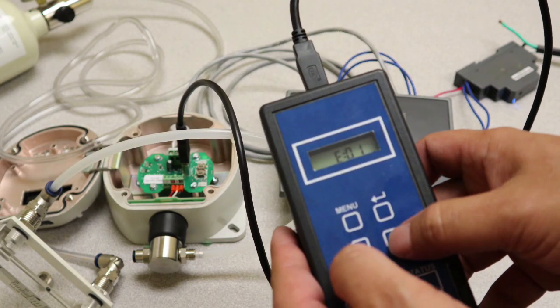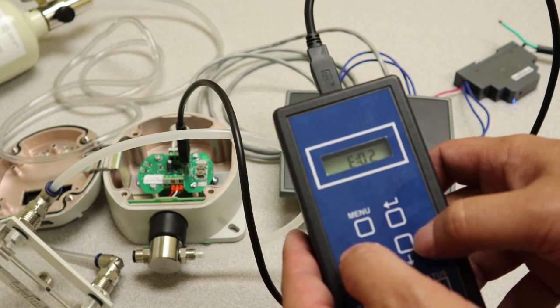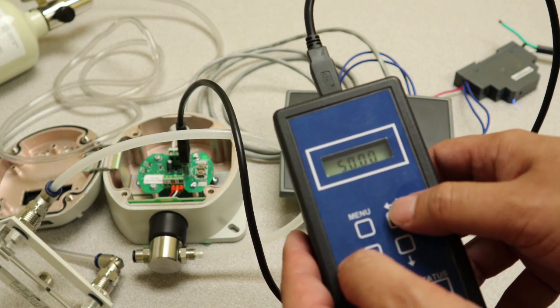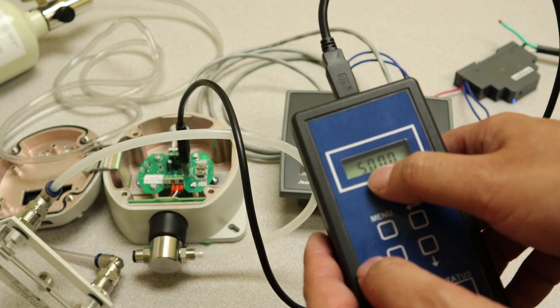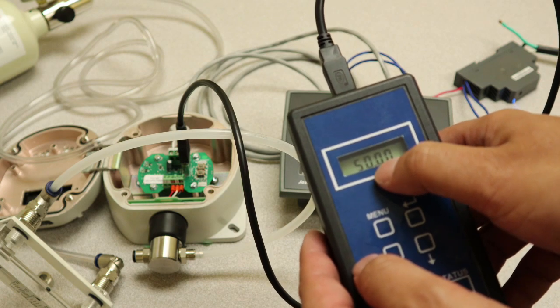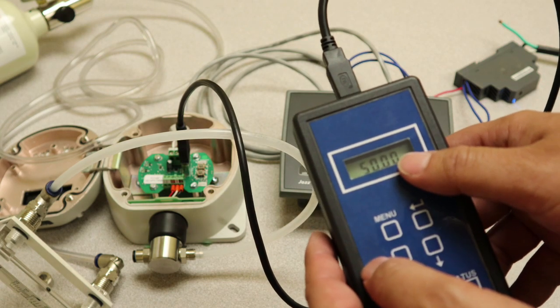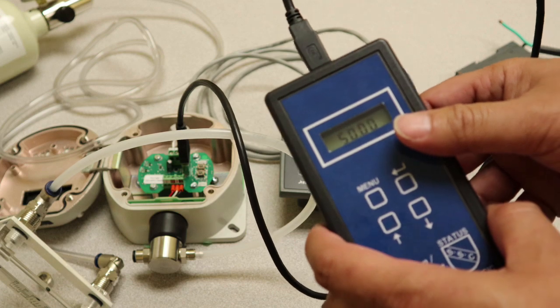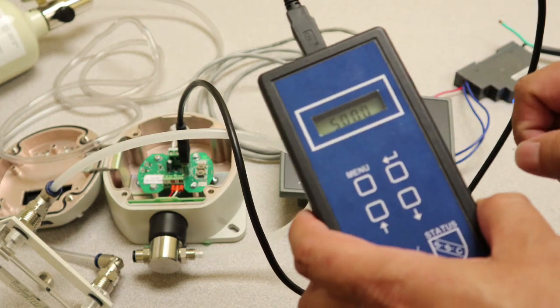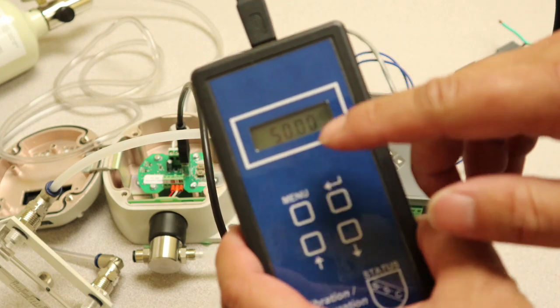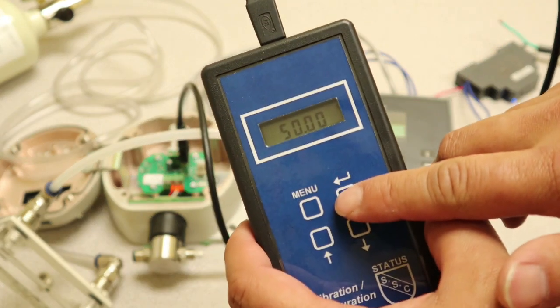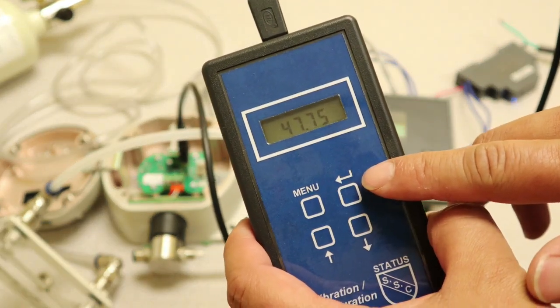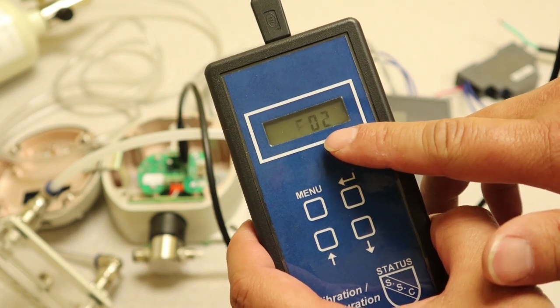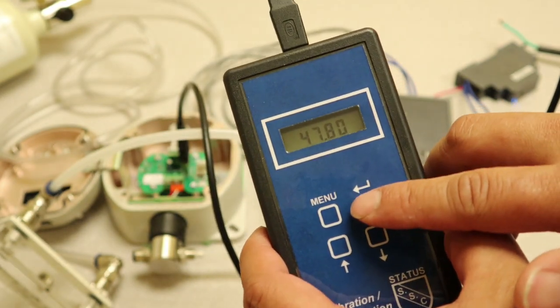Now this time we're going to go to E02. Hit enter. We're going to set the 50.00 to the gas that you're currently using. So if you have a bottle of 20 ppm, this is when you'll set it to 20 ppm. Right now I'm using a 50 ppm gas, so I'm just going to leave it alone and hit enter. It's going to flash that, and you're going to hit enter again.